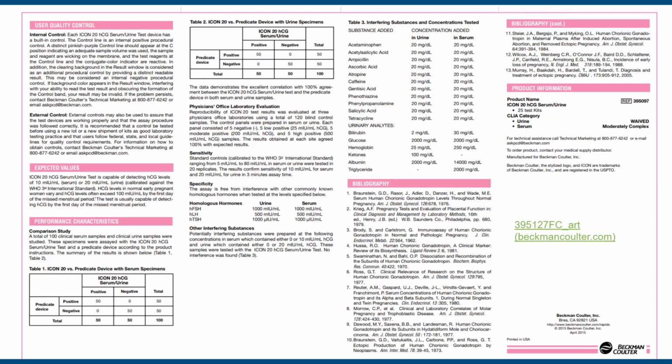And here it says external controls may also be used to assure that the test device is working properly. It's recommended a control be tested before a new lot or new shipment as good laboratory testing practice, and users follow federal, state, and local guidelines. So as long as your state or local guidelines do not exceed this manufacturer requirement, QC must be run each time you have a new lot or a new shipment of testing.